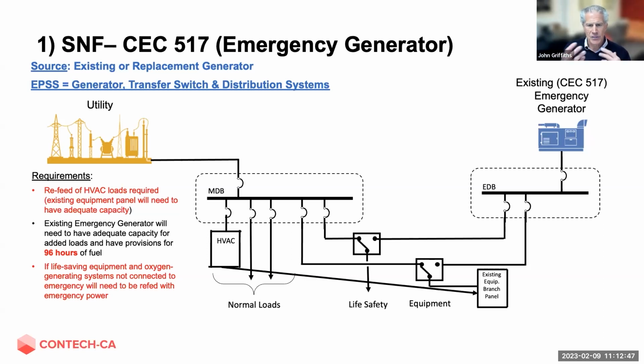If you have a design team or design-build contractor coming on board, we need to make sure you've transferred the connection to the equipment, but also all the various components that go with it. Controls - I know some facilities may still have pneumatic systems, or you need to make sure all the outstations for the BMS are connected, so when the generator comes back up, you're able to power, operate, and control the system.